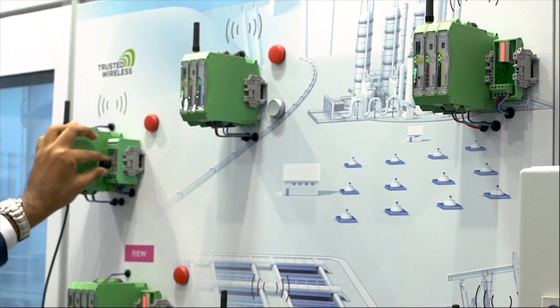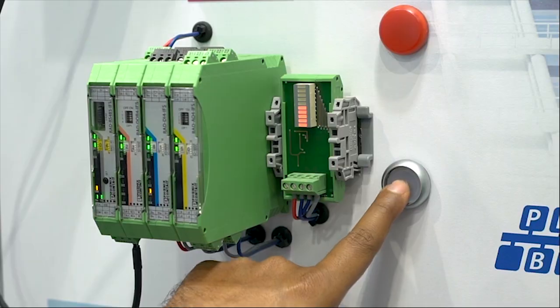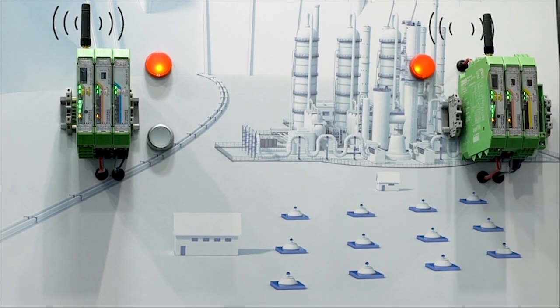You can use them in a wired way to integrate the RadioLine devices, and also we can communicate wirelessly. As you see here, we can connect analog inputs and collect the analog output from the other end, and similarly for digital inputs. The configuration is done using a thumb wheel, which is a very innovative, simple, and quick way of deployment.